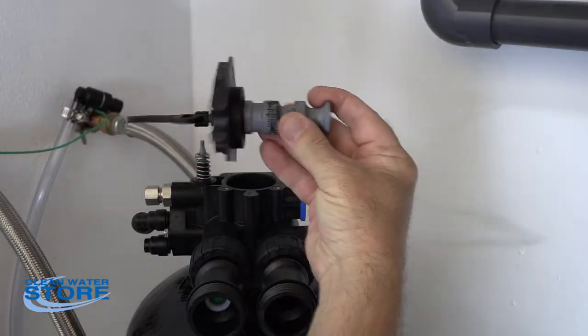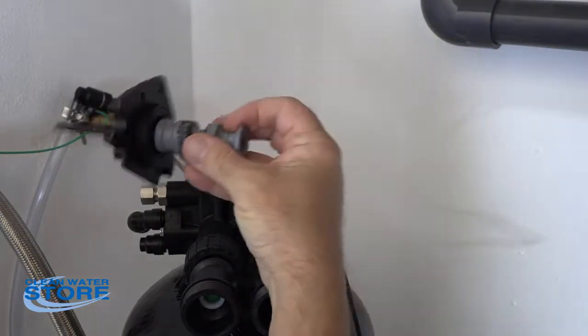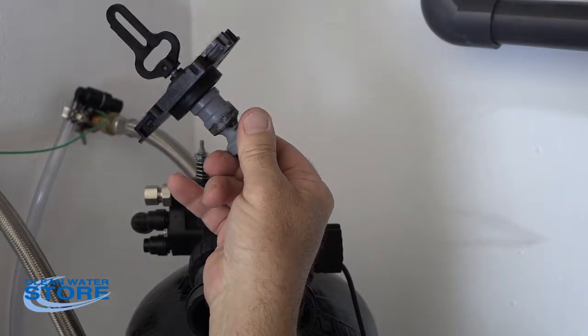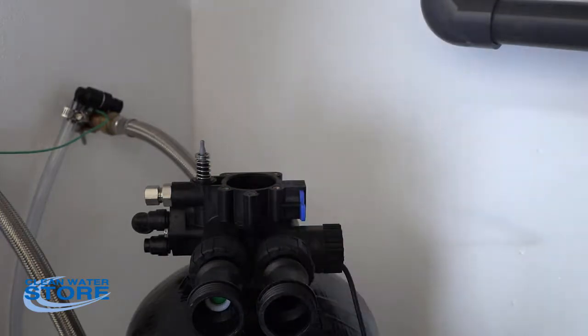This is one where a customer didn't service their valve for several years. As you can see, the gouges are really deep here. This piston assembly is going to need to be replaced now. So again, it's important to do this maintenance yearly.